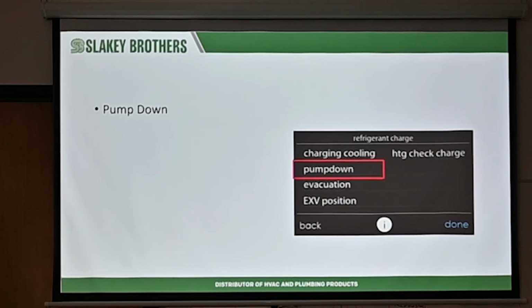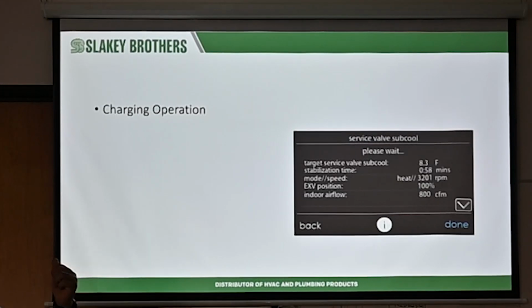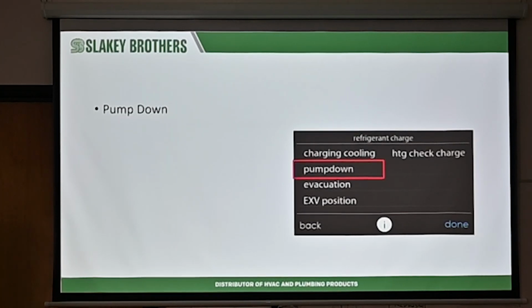Alright, pump down and evacuation. We're going to go through those here because if you ever have to do a repair on a 2-stage Evolution unit, you can push in the contactor, close the valve, push in the contactor, pump it down. Pretty simple. But there's no contactor here. We're taking single phase voltage, converting it to a 3-phase AC signal to modulate the condenser, the compressor, up and down. So there's no real way to do it, but our controller can do it.